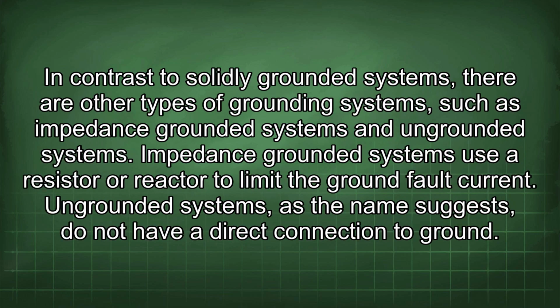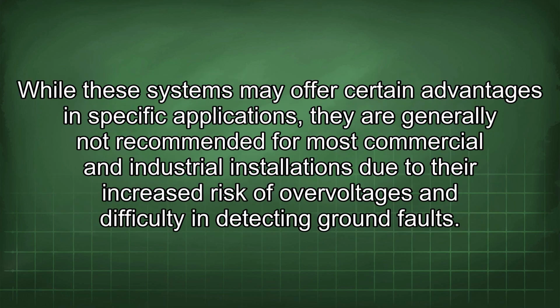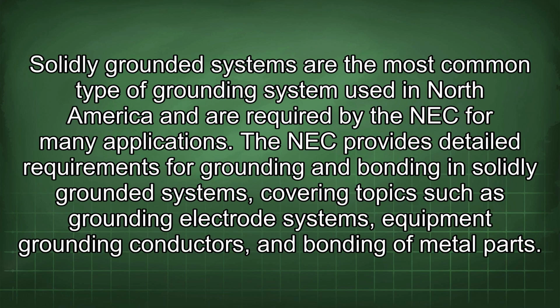In contrast to solidly grounded systems, there are other types of grounding systems, such as impedance-grounded systems and ungrounded systems. Impedance-grounded systems use a resistor or reactor to limit the ground fault current. Ungrounded systems, as the name suggests, do not have a direct connection to ground. While these systems may offer certain advantages in specific applications, they are generally not recommended for most commercial and industrial installations due to their increased risk of overvoltages and difficulty in detecting ground faults. Solidly grounded systems are the most common type of grounding system used in North America and are required by the NEC for many applications. The NEC provides detailed requirements for grounding and bonding in solidly grounded systems, covering topics such as grounding electrode systems, equipment grounding conductors, and bonding of metal parts.